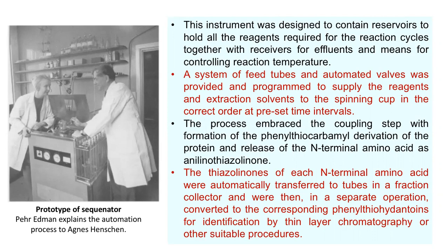And this instrument was designed to contain reservoirs to hold all the reagents required for the reaction cycles, together with the receivers for effluents, and to control the temperature, the pH, and all those things. And all these things were preset at time intervals so that one after the other, the reactions would continue taking place. That means it was all programmed.